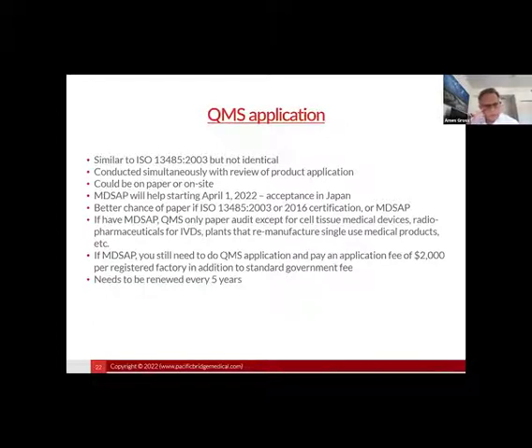So we also talked about the QMS application. As you know, the QMS application is required as well as the dossier, STED, and FMR application. The QMS is similar to ISO 13485, but it's not identical, so keep that in mind. It could be a paper audit, we talked about that. Japan is going to start accepting MDSAP applications as of April 1st this year, 2022. And basically there's a better chance of just doing a paper audit as opposed to an on-site audit if we have the ISO certificate or the MDSAP.